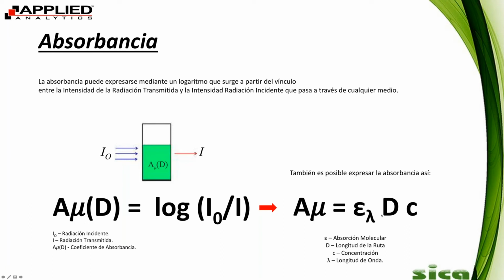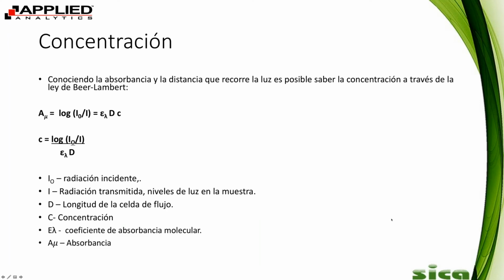The D is the distance of the path length. Sometimes we have very, very short path lengths. So say, for example, you're measuring a high H2S application. H2S has a lot of absorbance, so you don't need a long flow cell. So we'd use, like, a 2 millimeter flow cell or something like that. If we're going down to low concentrations, we're going to go up to a long flow cell. So the D, the distance of the flow cell, matters when calculating concentration.